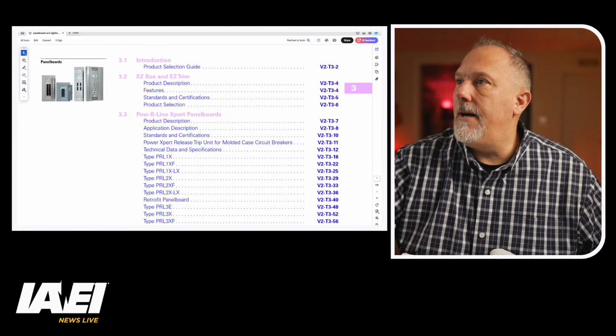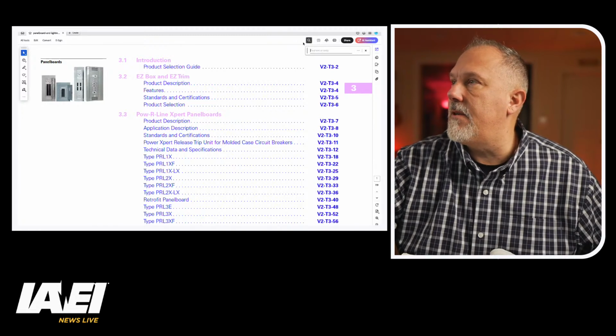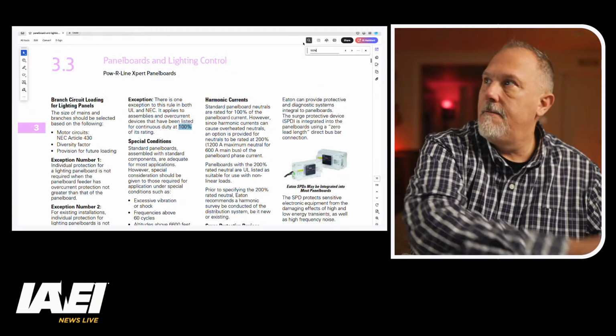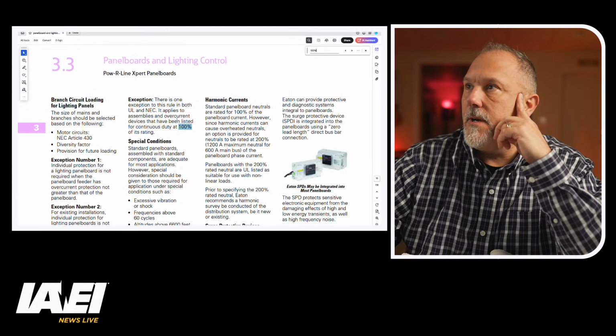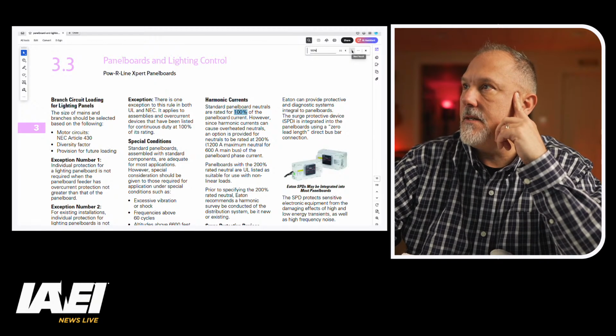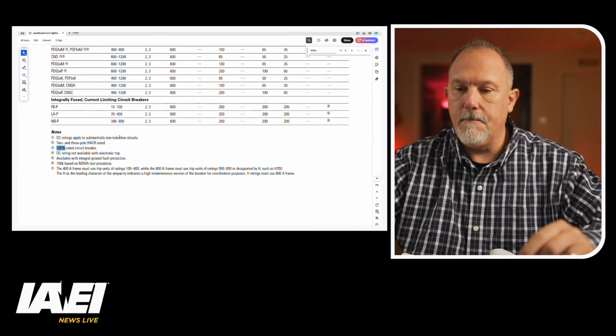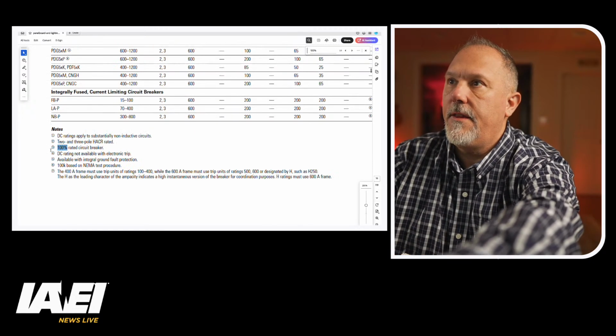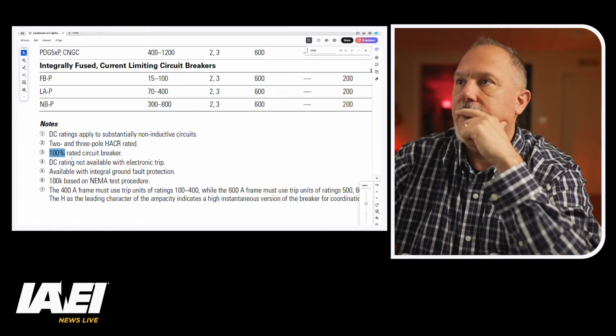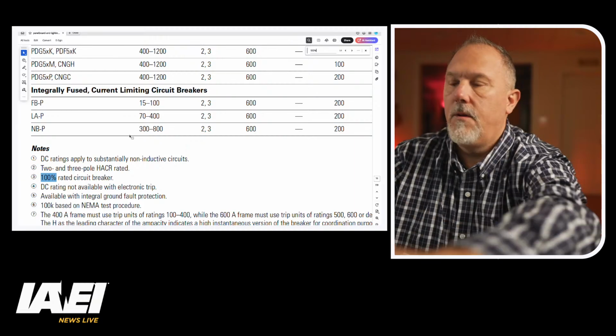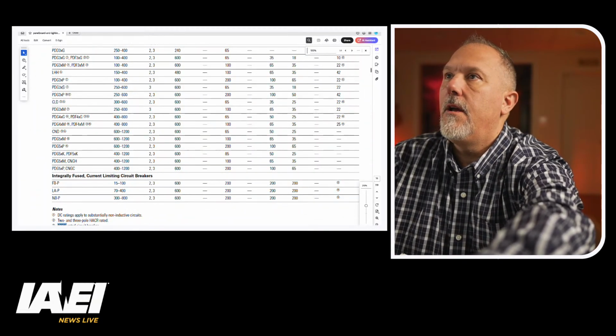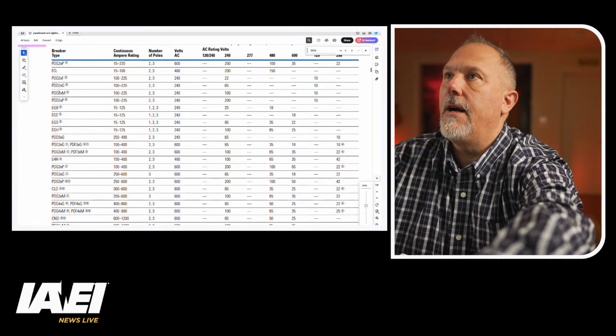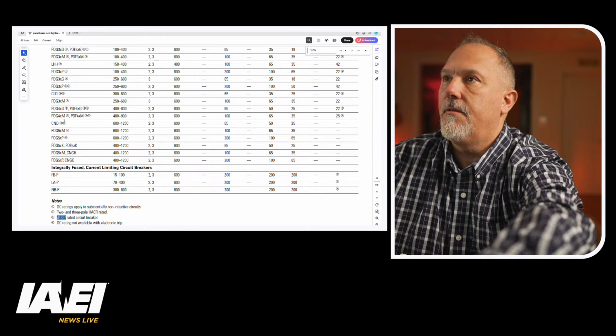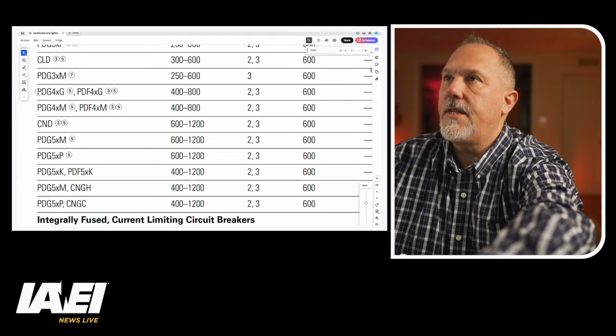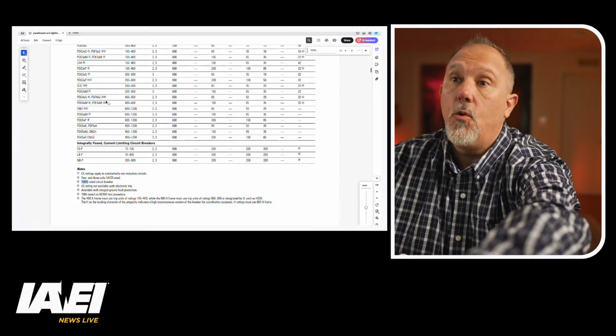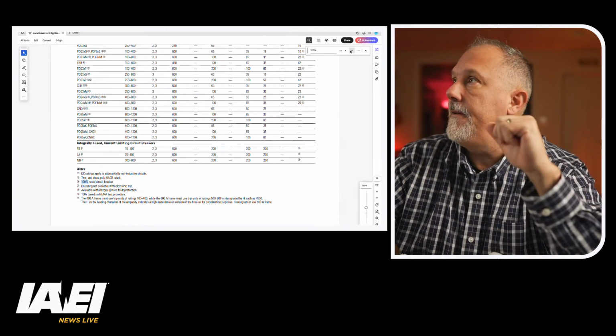All right, so if I come into this PDF and I'm going to search for 100%, there's one exception to the rule. Both UL, it applies for 100% of its ratings. You'll see a note in this here. It says 100% rated circuit breaker, note 3. So not all circuit breakers are 100%. These here have the note 3 next to them, so that tells you which circuit breakers are 100% rated.